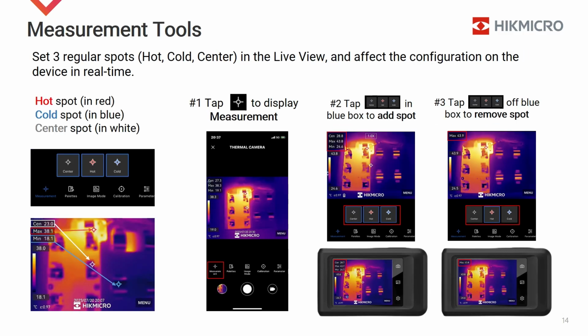This time, let's focus our eyes on measurement tools on the live view interface. You can turn on or off 3 regular spots for the device and the Viewer app. They are respectively hot spot, cold spot, and center spot. The hot spot is in red color, representing the maximum temperature in the whole screen. The cold spot is in blue color, indicating the minimum temperature in the screen. The center spot is in white color, reflecting the temperature in the center.